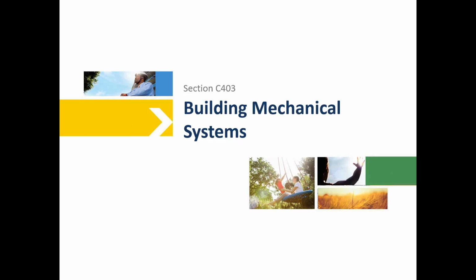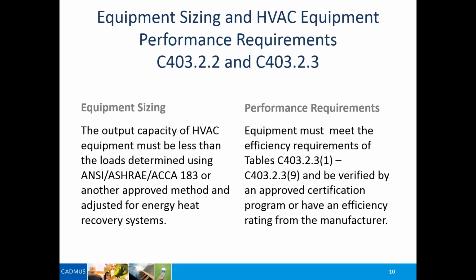The systems we're going to be looking at, again, are systems that basically provide space conditioning. The old code used to say human occupancy. We don't use that term anymore, but it's space conditioning for the building to make sure that our occupants are as comfortable as they possibly can be in those buildings. So we're not going through everything, but going through some of the highlights that are in the mechanical requirements. One of the first requirements that's currently in your 2006 code, and has been in every code after that, is essentially making sure your system is sized properly to meet the demands of the building.